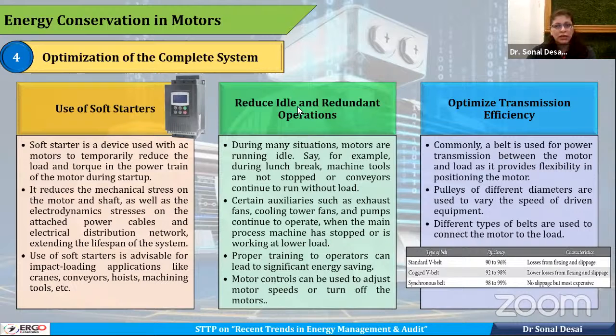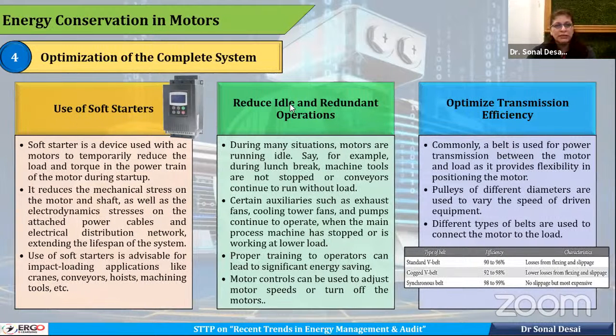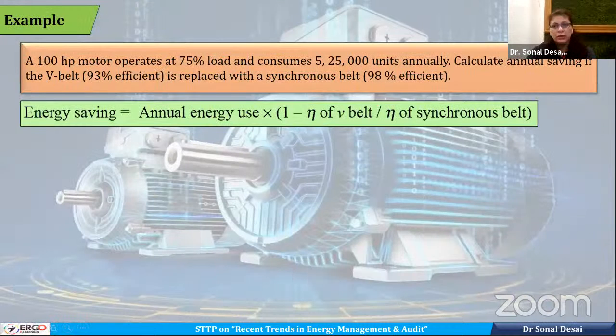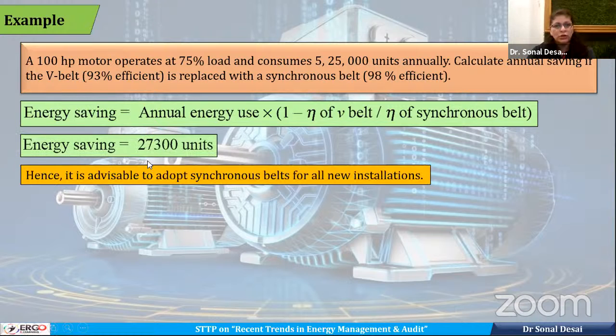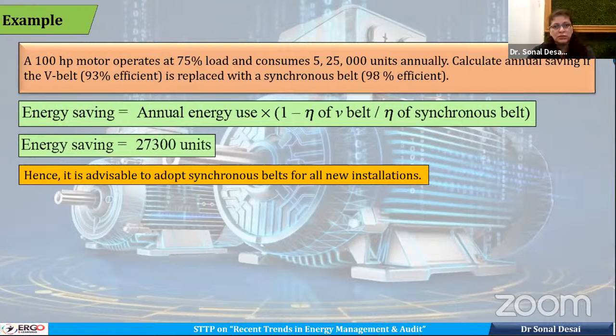So here there is one case study shown: a motor which operates at 75% load and consumes 5 lakh units annually. Calculate the increase in efficiency if we shift from a V belt, which is 93% efficient, to a synchronous belt, which is 98% efficient. Based on annual usage, it is shown that 27,000 units are saved by just replacing the belt. Hence, replacing the belt is advisable because that costs almost nothing.